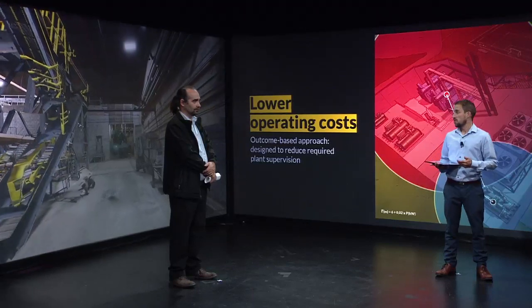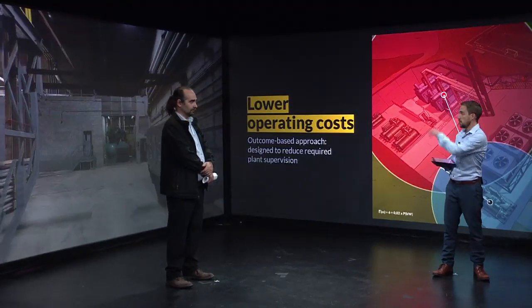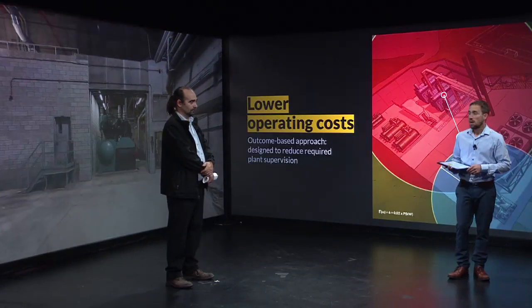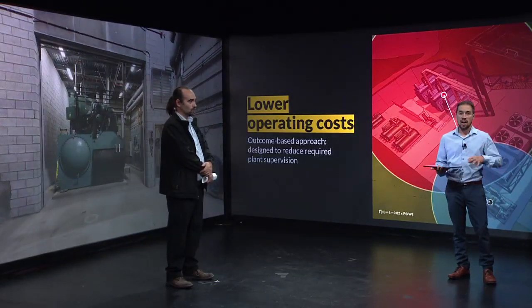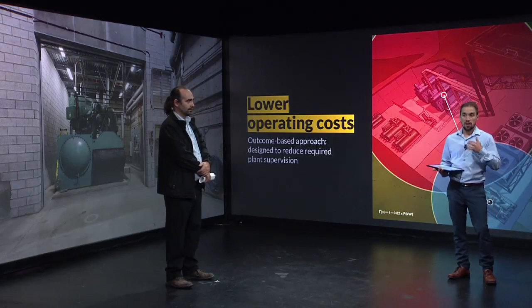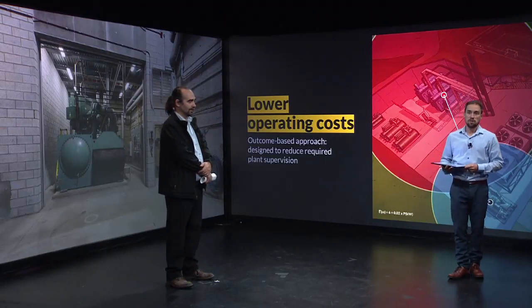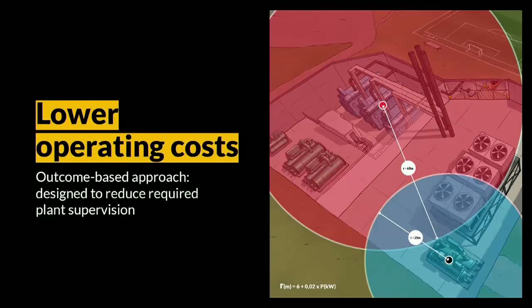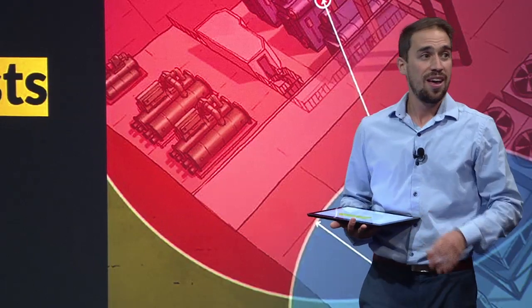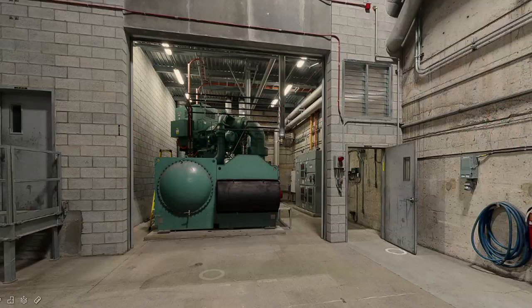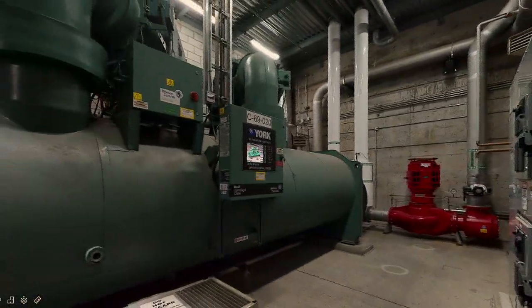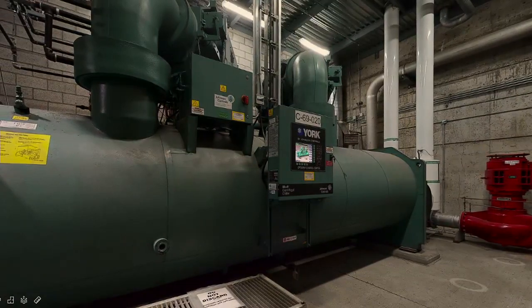So one of the things we did was relocate the bigger chiller, a 2,000-ton chiller, out of the central plant so it doesn't count as central plant equipment, in order to reduce the total amount of chillers there. We actually had to build a mechanical room because it's located in the cooling tower area, and it's about 1 inch from the minimal distance, otherwise it would be counted as central plant equipment. So it was really tight, but that's what we needed to reduce the surveillance to 1 hour a day.